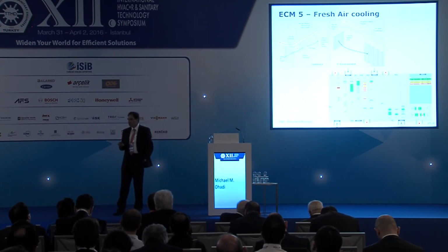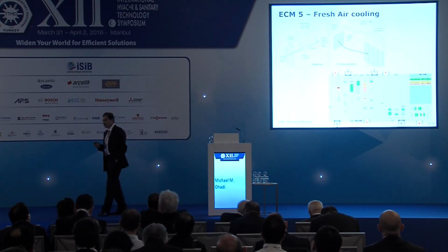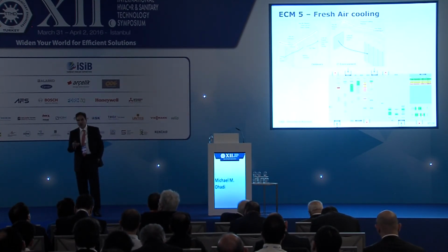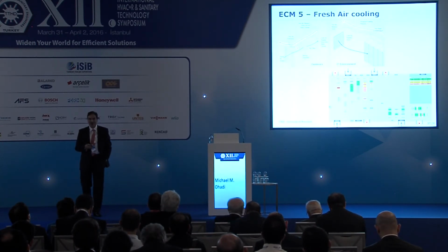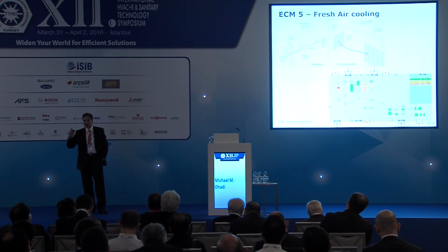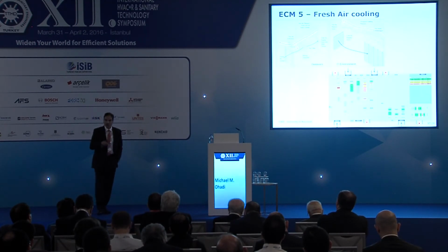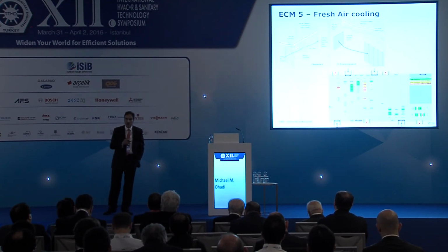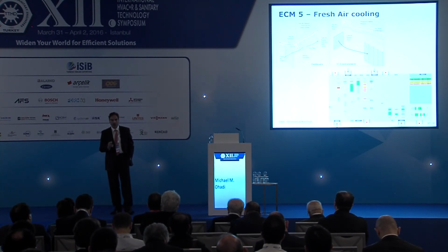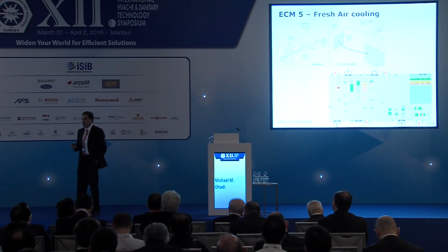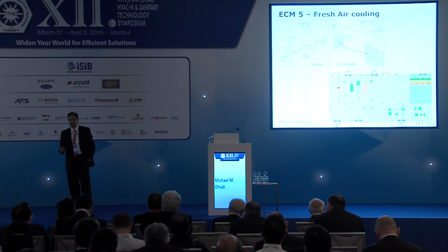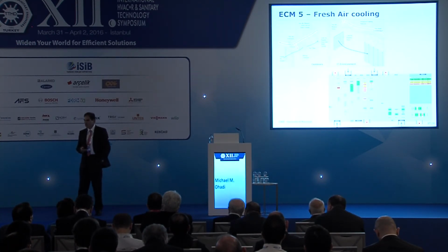The only time you have to be careful with fresh air cooling is when you're in downtown Beijing, or downtown - I'm not sure how polluted the air is in Istanbul - but if you're operating in a very polluted environment, the acidic stuff that comes in with the pollution could cause damage to the servers. Your insurance company wouldn't like it, and your policy premiums would go up immediately. Other than that, if you're in the suburbs or places where the air is free of pollution, you can just filter with regular filters to get the dust out, and you'll be fine.